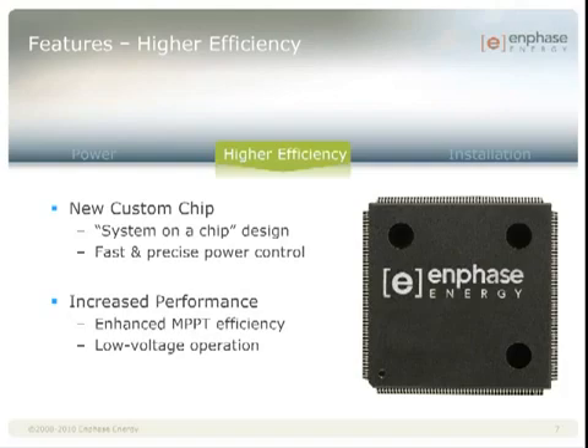We're at 96% conversion efficiency, with a maximum power point tracking efficiency of 99.8% static and 99.9% dynamic. One other compelling aspect of our digital control is that it enables very high conversion efficiency at low power levels. Thanks to a unique capability called burst mode, there is no drop-off in efficiency as the input power decreases below 20%, which is unique among inverters.